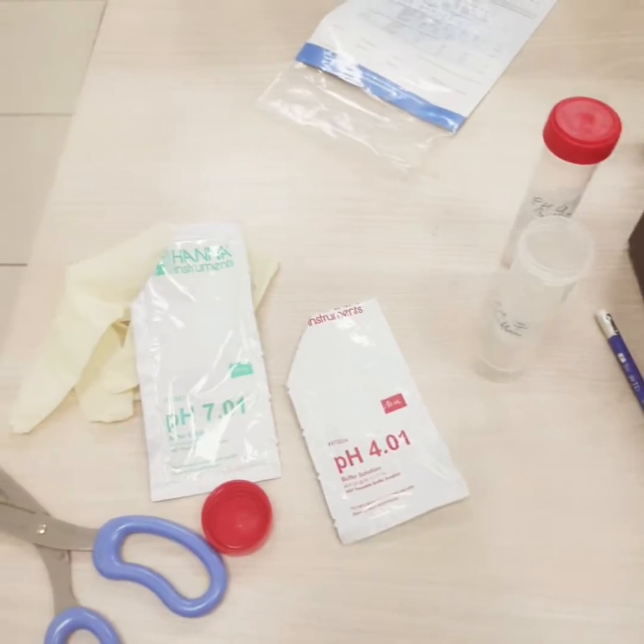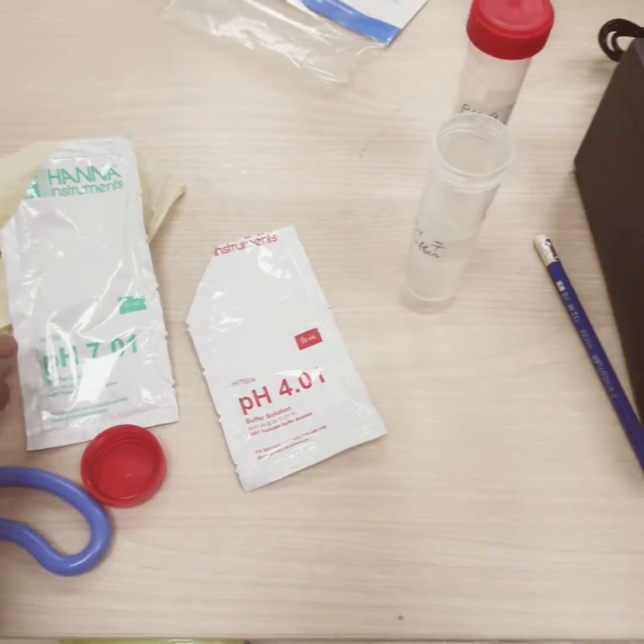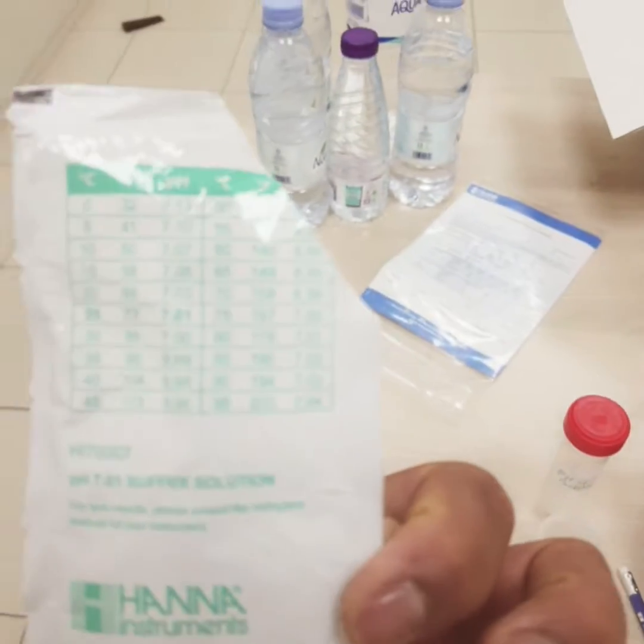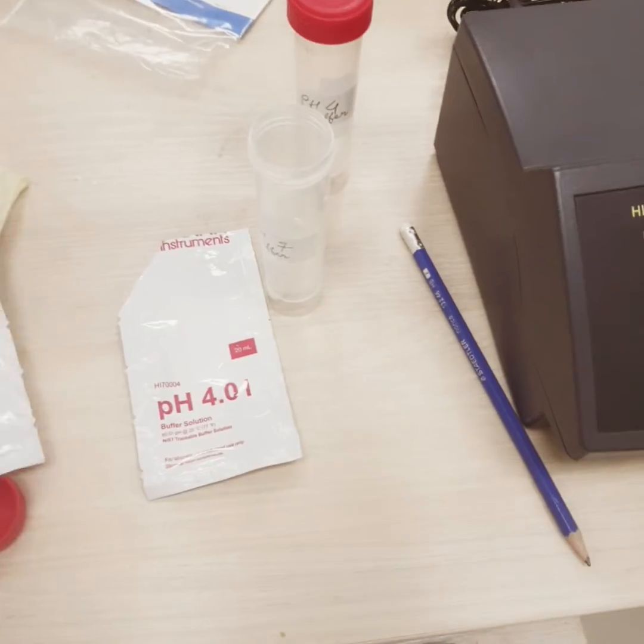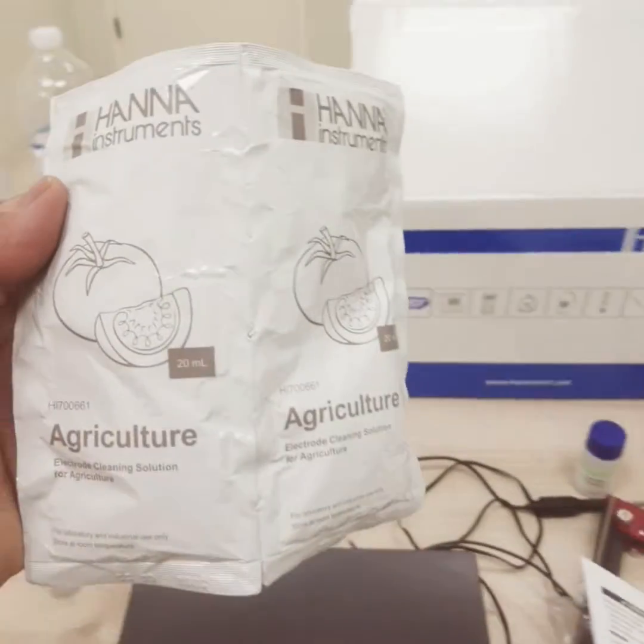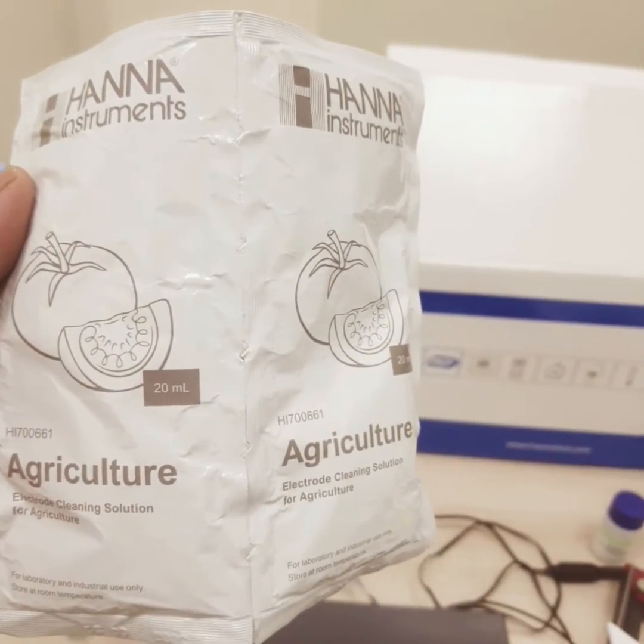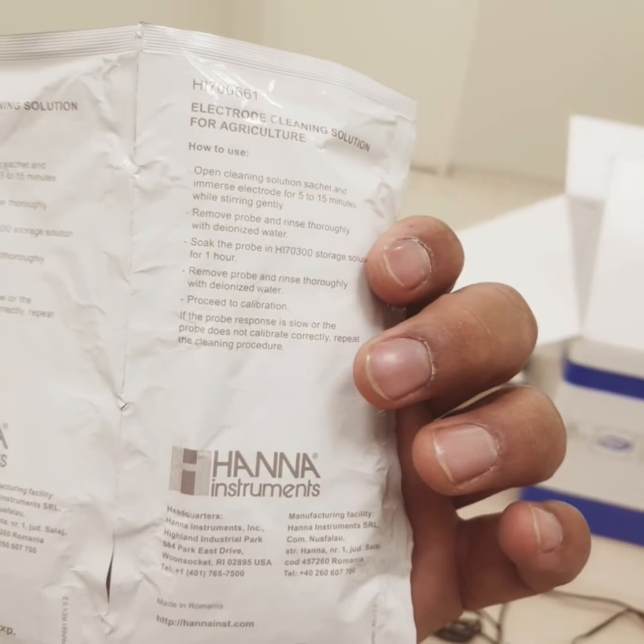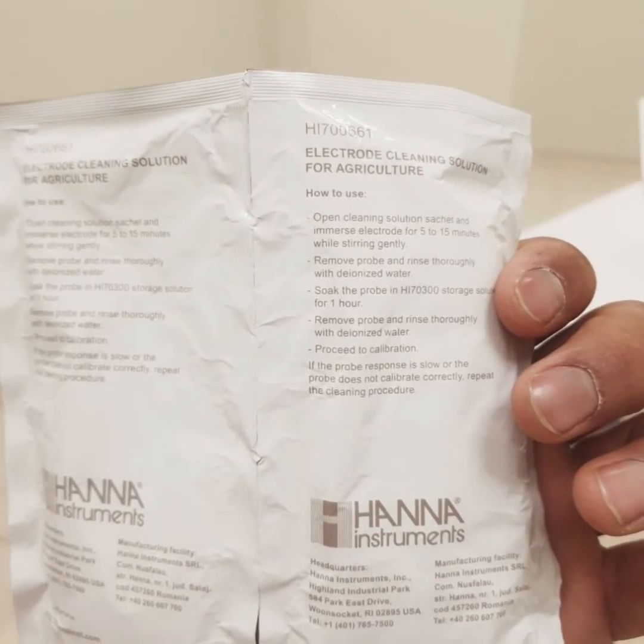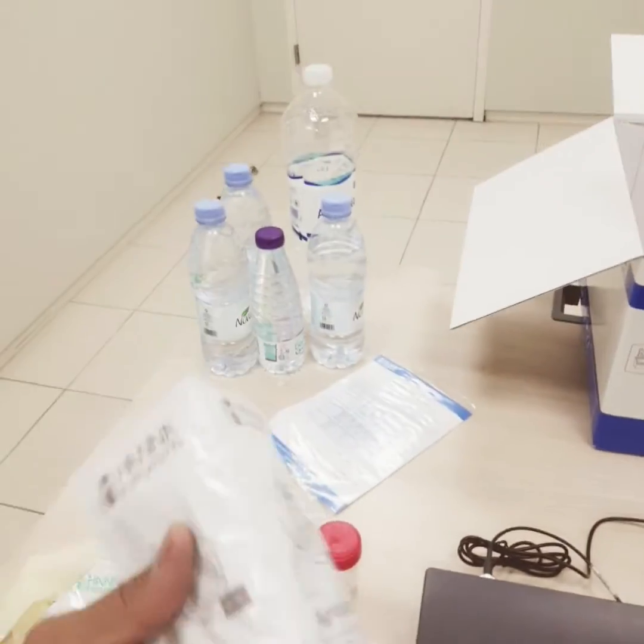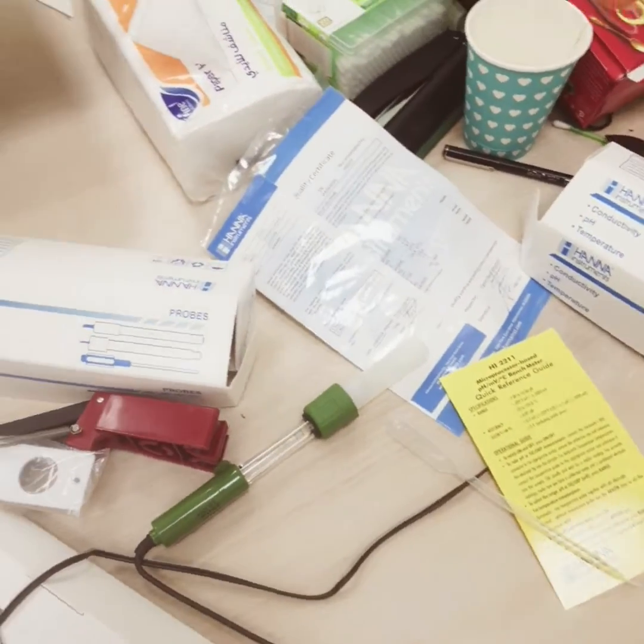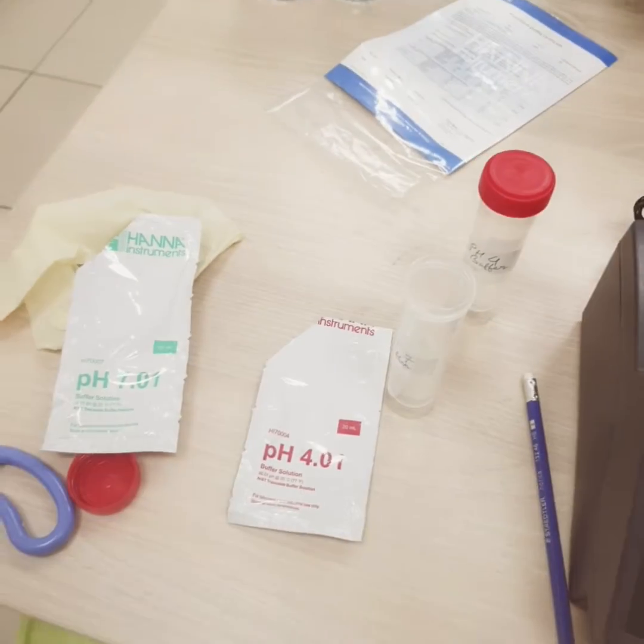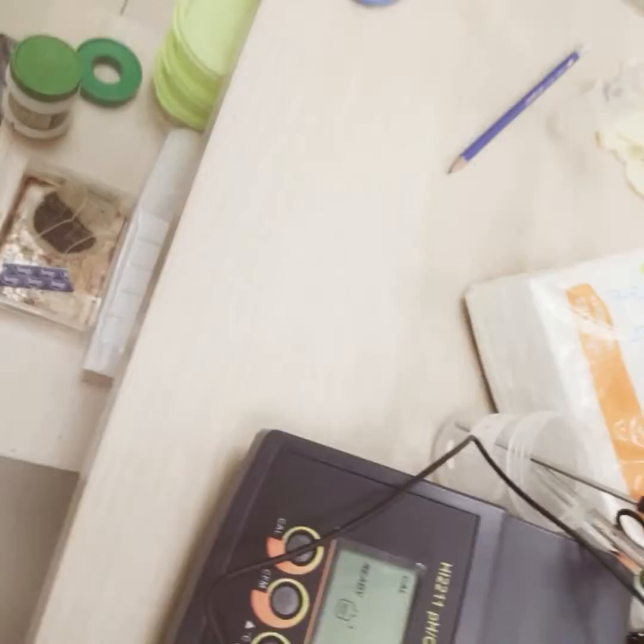Now I have transferred these buffers from this sachet to the vials. So there is also a lot of information here. It's the temperature dependence of the pH, and here also, and here we have one more thing. So these are electrode cleaning solutions for agriculture. Okay, so if you are using some dirty samples, you can clean and then start the calibration. Already the probe is new, we don't need to clean it. So now we'll start the calibration procedure. Now I have added the buffer solution, and also added the probe.